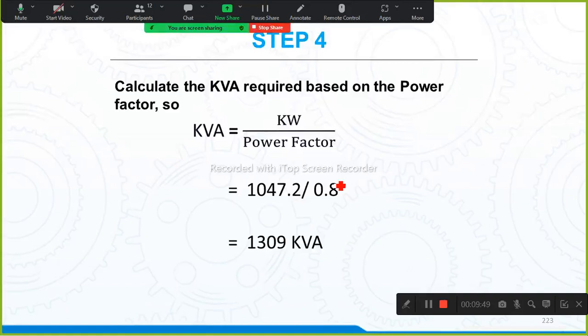That is equal to KW is 1047.2, which you got. Power factor is always the default power factor, which is 0.8. So when we calculated the KVA, we got 1309 KVA. तो ये पूरा बिल्डिंग लोड को मुझे पावर देना है, तो कितने से इसका ट्रांसफार्मर लगाना है? 1309 KVA. But we know that any transformer will not give any 100% efficiency.